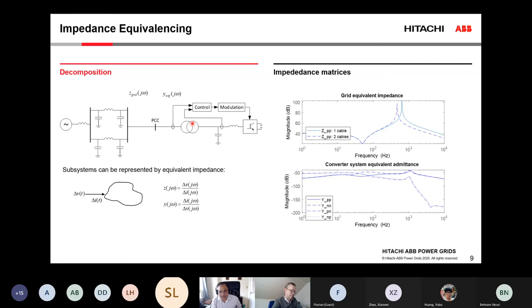So it's still not clear actually whether we can call it a harmonic instability or a resonant instability. Harmonic instability can be the cause of the switching of your converters, where the switching frequency will have some kind of multiplicity with the power frequency. Whereas the resonance can be even without any harmonics, but we have cables which have inductance and capacitance, and its electrical characteristics purely can pose, as you showed in your impedance picture. So it can be like this. So that is the thing that I wanted to ask you. How do we then distinguish between harmonic instability or instability due to resonance?